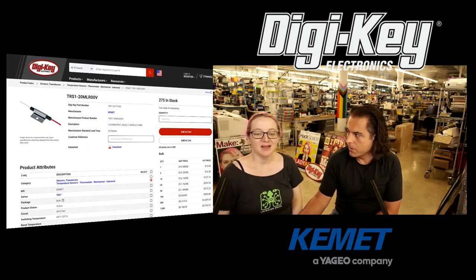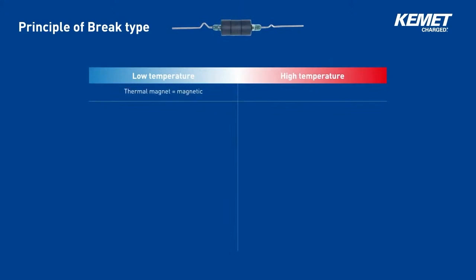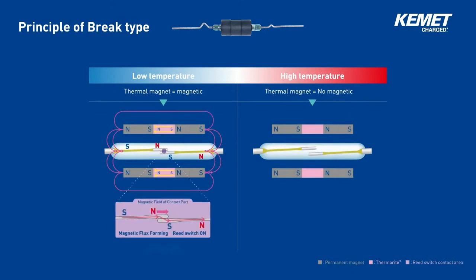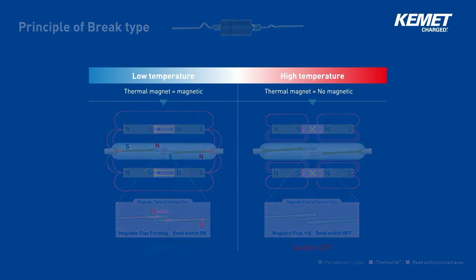We have a little video snippet that has some information about that. Let's shift our focus to the operation principle of the thermosensor. Simply put, it is a thermal switch that opens and closes the contacts within its built-in reed switch by the shift in magnetic energy of thermorite and permanent magnet. A ring-shaped thermorite is in the sensor, sandwiched by two ring-shaped permanent magnets with polarity arrangement as shown, with a reed switch fixed inside the rings. When the temperature of the thermorite is at or below its Curie temperature, it functions as a magnetic body. When the temperature exceeds the Curie temperature, it becomes a non-magnetic body. This change in characteristics shifts the magnetic circuit, which makes or breaks the contact in the reed switch. The thermal sensor has two types of switching action — break type and make type.